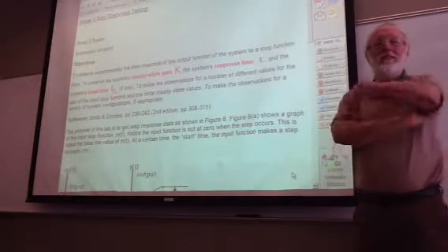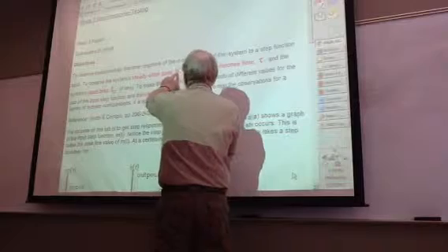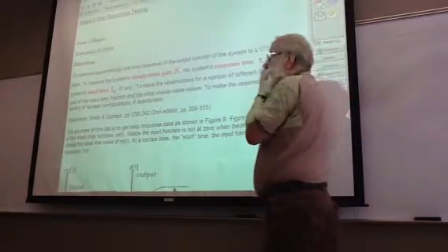Sweet. 2 classes. Any question on what that means? These are the 3 parameters that you're going to be looking for. The gain, steady state gain, which has the symbol K. The system's response time, which I told you we're going to call tau. And then there's something that wasn't even on that other graph. It's dead time.